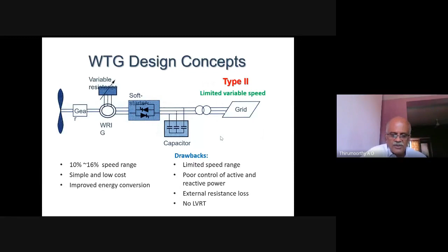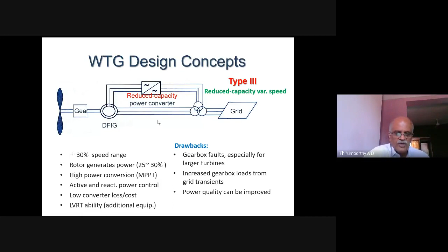Then came the type 3 machines, commonly called DFIG, double fed induction generators. Even the rotor contributed to the energy conversion. Nearly 15 to 20% of the energy would be supplied by the rotor also, with limited control on the active and reactive power. In these machines, LVRT capability was there. Most of the machines supplied after 2014 were this type, and there was improved power quality in these type of machines.